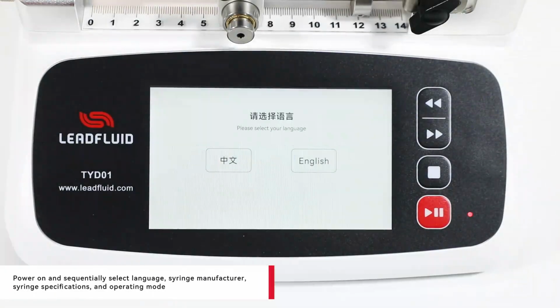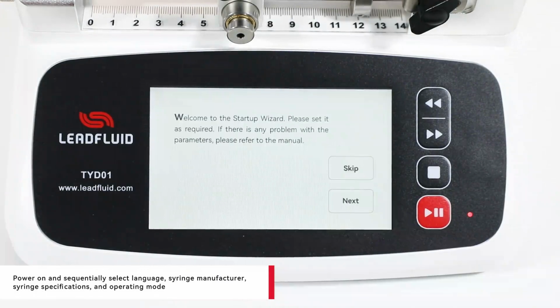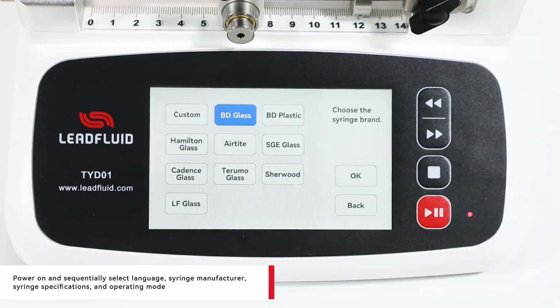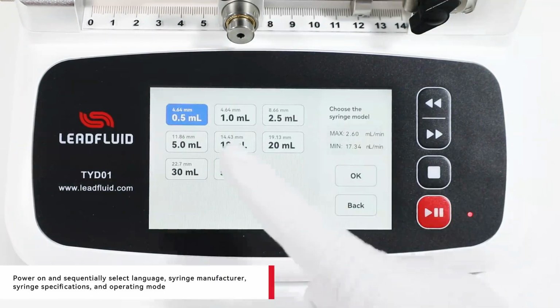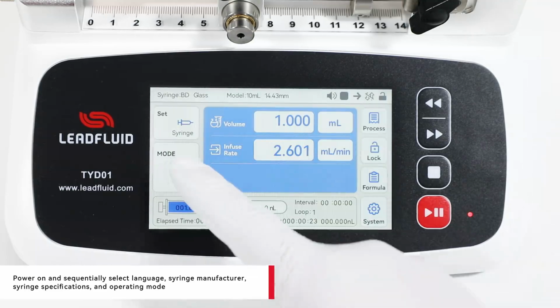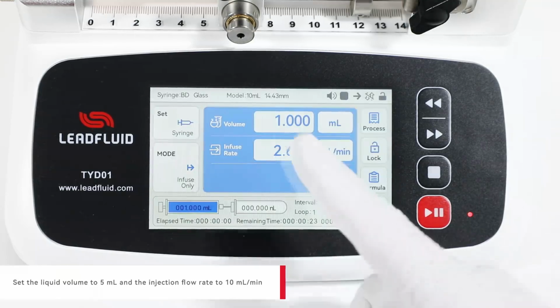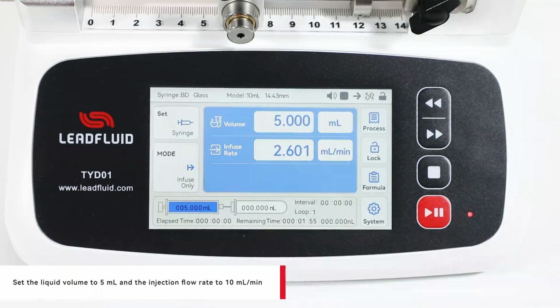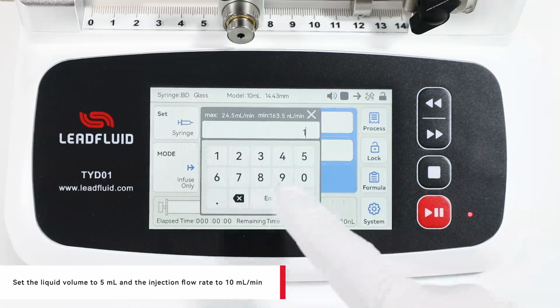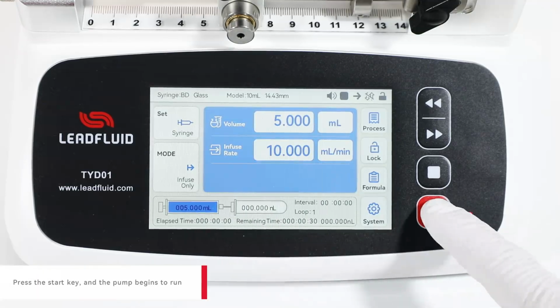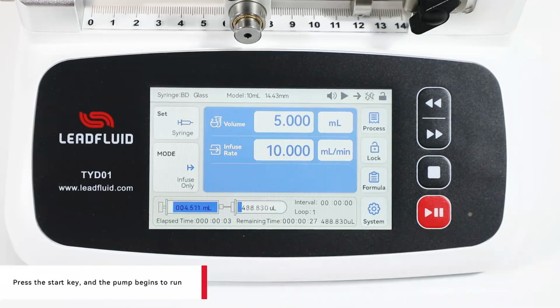Power on and sequentially select language, syringe manufacturer, syringe specifications, and operating mode. Set the liquid volume to 5 ml and the injection flow rate to 10 ml per minute. Press the start key and the pump begins to run.